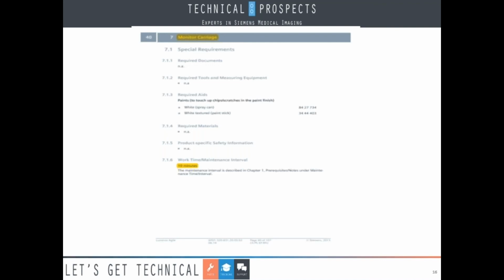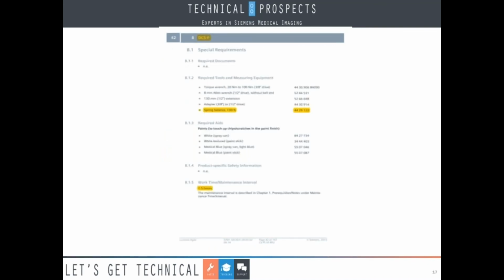This one is for a monitor carriage, and being Siemens, they also call it a monitor cart - might be confusing to people, but it's the same thing. They're only giving you 10 minutes on it, so it's important to add up your time and see, because you might take only 5 minutes, or you might have problems and take 15 minutes. With this chapter you might want to perform it at the same time as a collimator check, since you need that tool. Unless you carry one regularly, look at the whole document and find out which chapters need a spring balance so you can do them all at the same time.